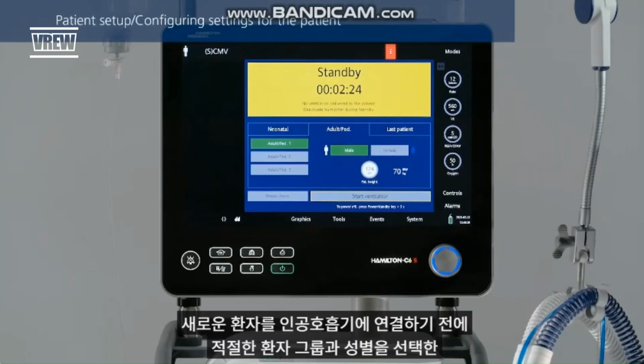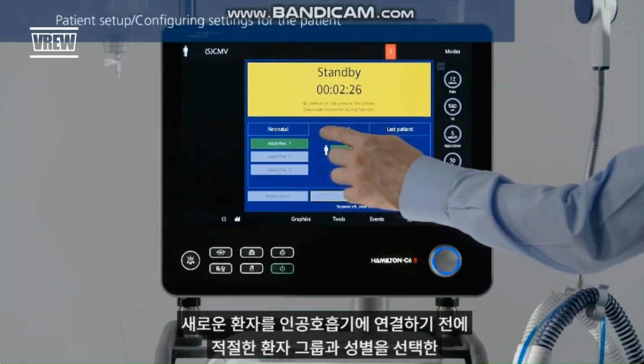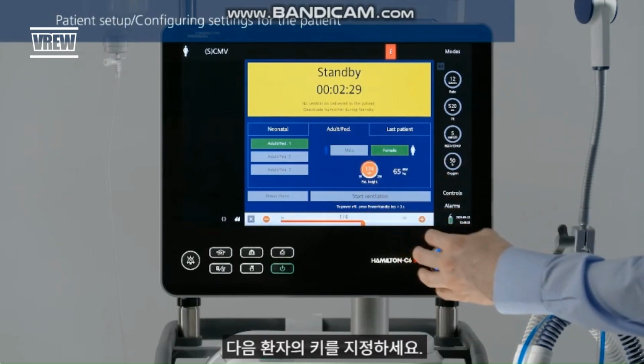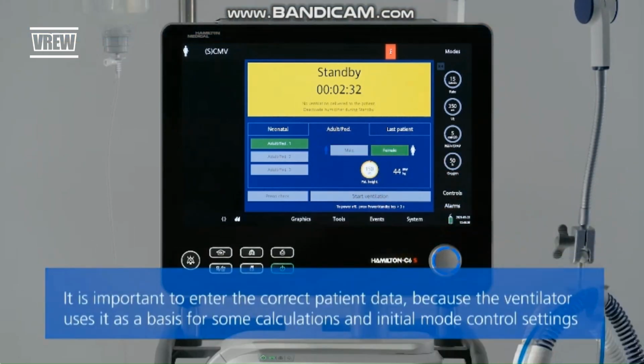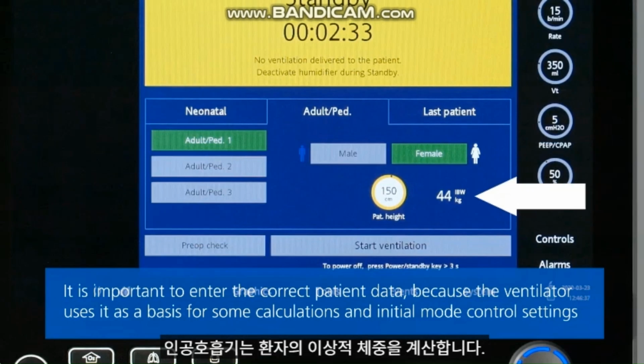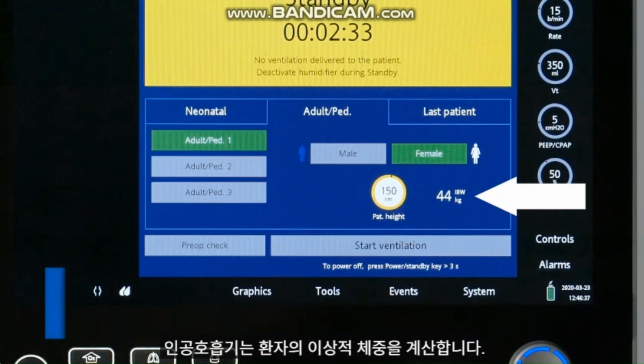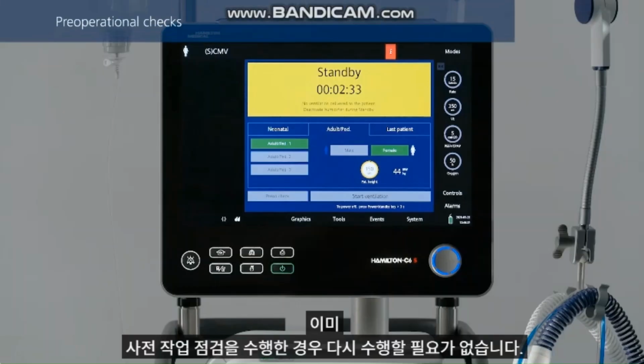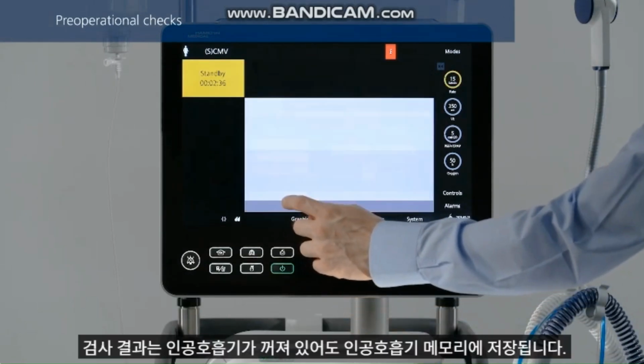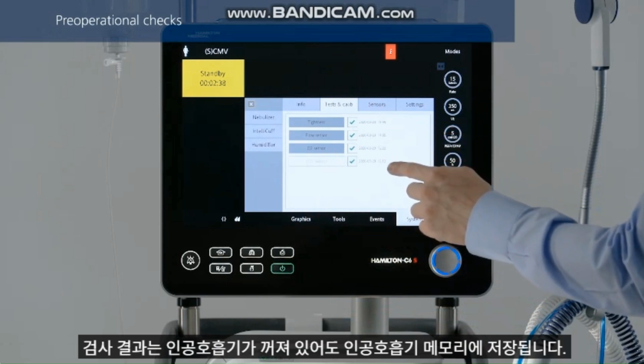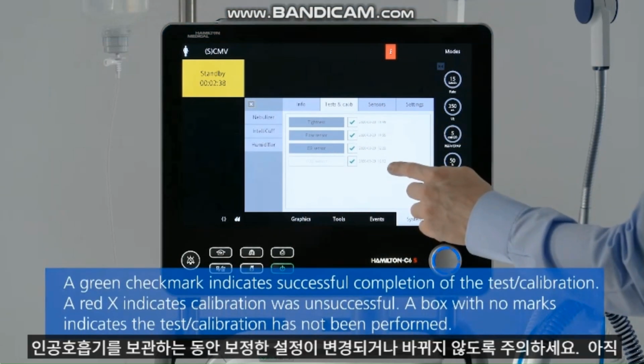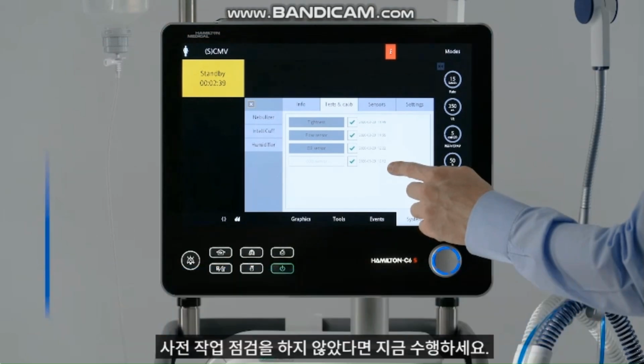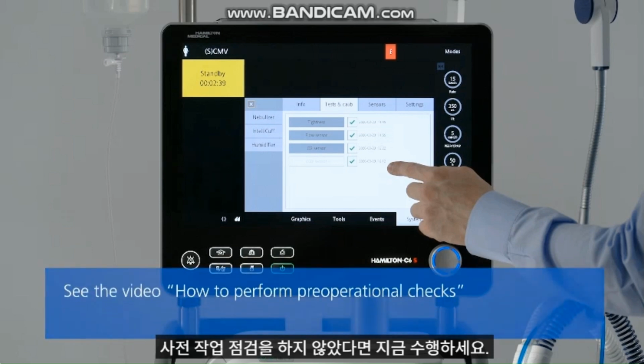When connecting a new patient to the ventilator, select the right patient group and sex, and then specify the patient's height. The ventilator calculates the patient's ideal body weight. If you have already performed the pre-operational checks, you don't need to repeat them. The test results are stored in the ventilator's memory, even when it is turned off. Make sure that the setup you calibrated is not changed or altered while the ventilator is in storage. If you haven't already done so, perform the pre-operational checks now.